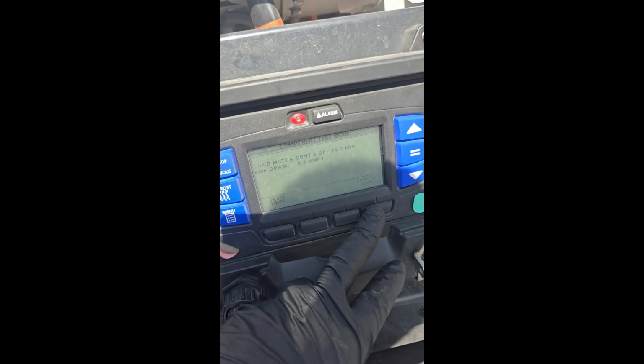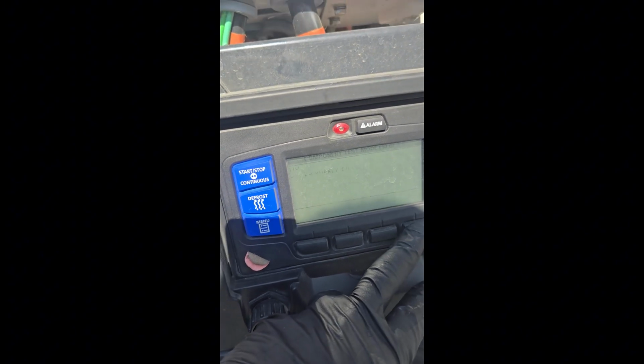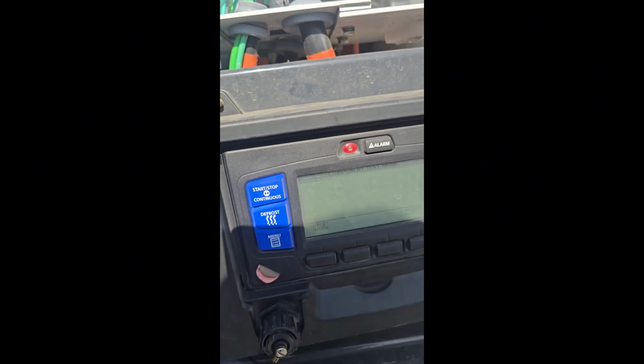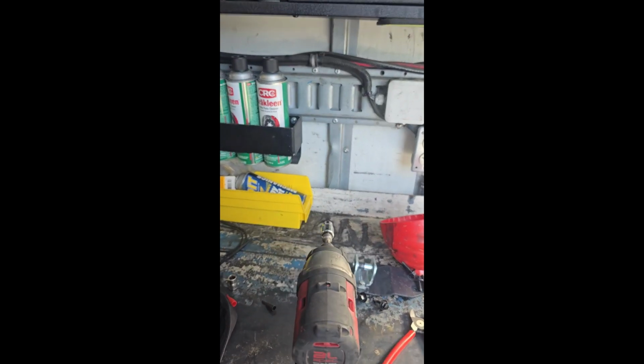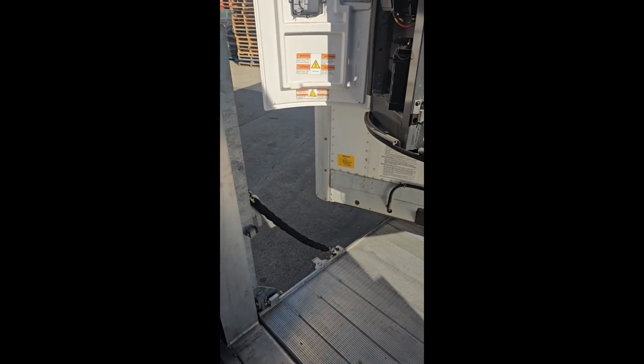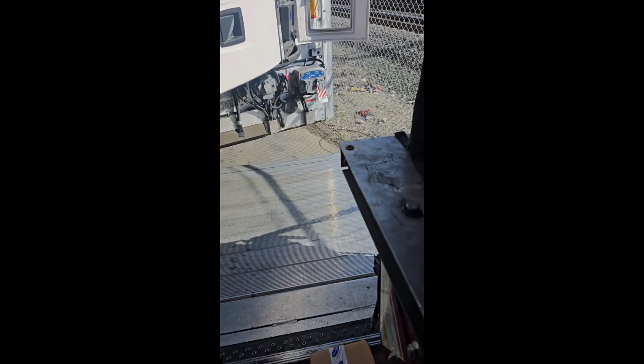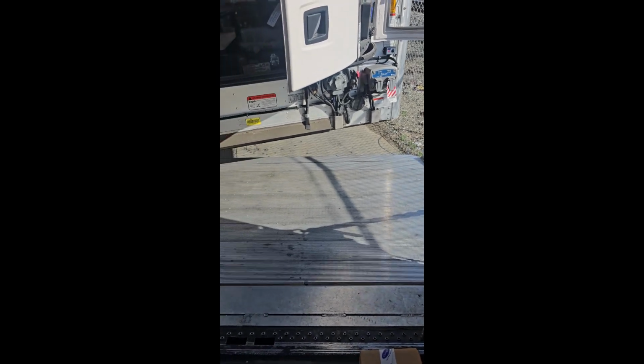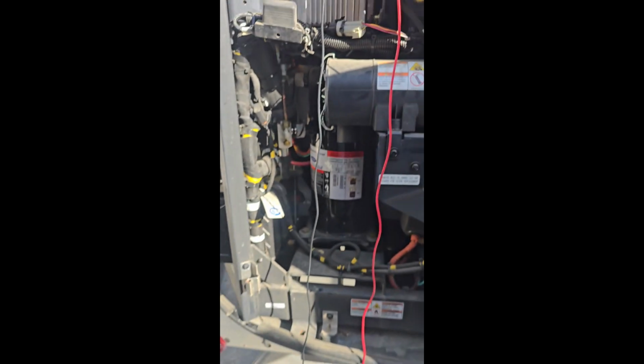Now, to double check that, we're going to come back over here, exit our test mode, and go back in one more time. I'm going to do something that helps make diagnostics a little easier. Since I know my fan circuit is open, I'm going to jump the connection with these guys right here and see if my contactor energizes.